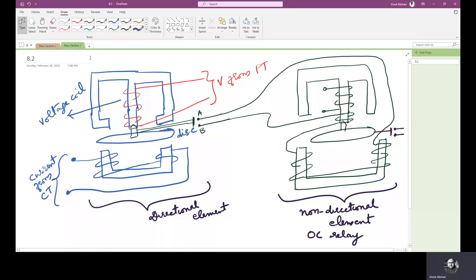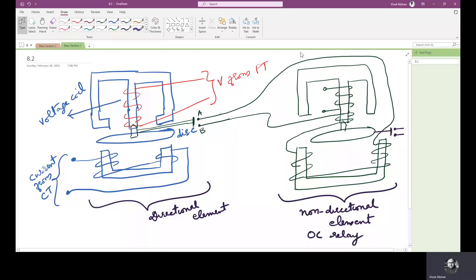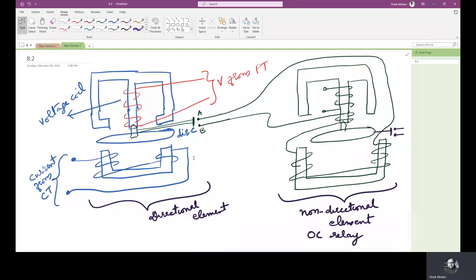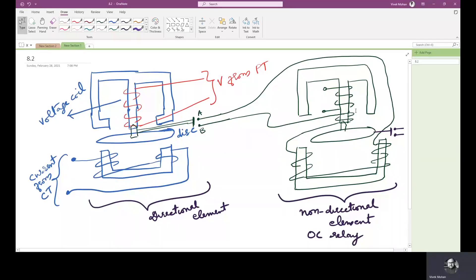These two conditions must be satisfied. The first is the directional condition. Once the directional condition is satisfied, the A-B contact will close. If this is closed, this is connected to the non-directional element, which will make the disk move if the current is more than the pickup value. Under normal conditions, power flows in the proper direction and hence the directional element of the relay is inoperative, so it will not activate the second non-directional circuit either and the relay will not send a trip signal.